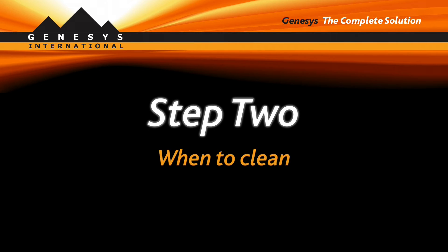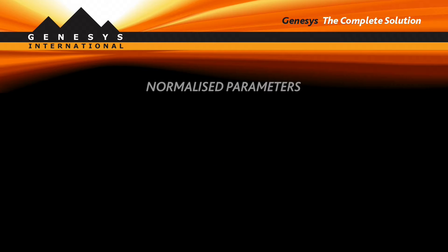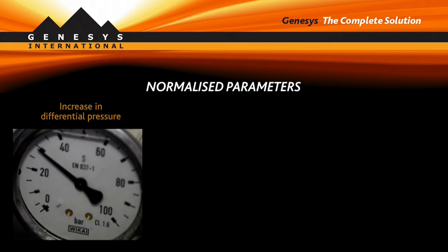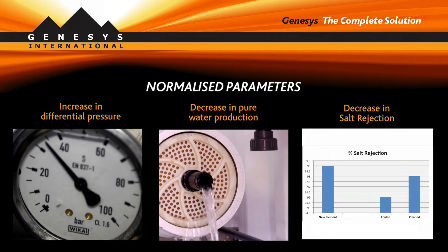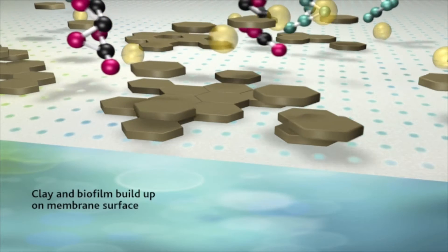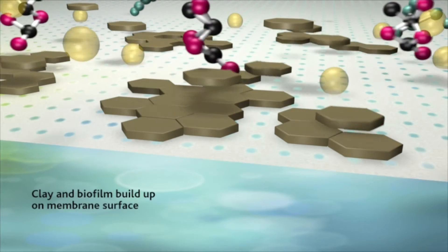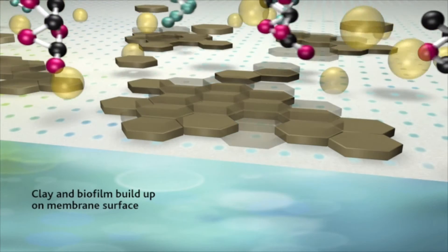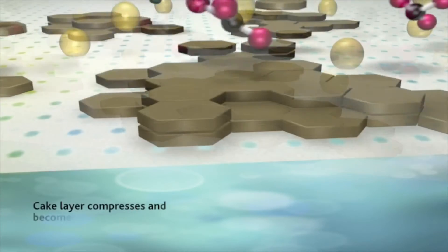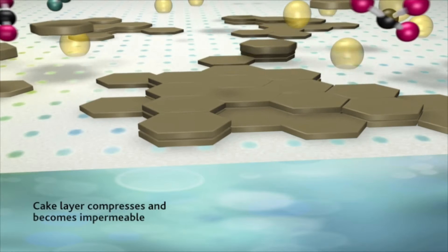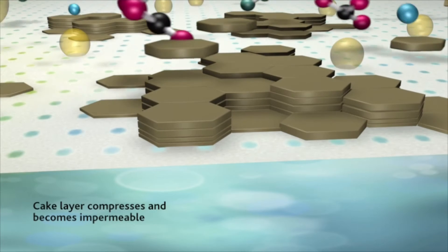Step 2: When to clean. Membrane manufacturers recommend cleaning when normalized parameters change by 10–15%. Delaying cleaning causes foulant compression into the membrane, making removal more difficult. Extra cleaning cycles require more time and chemicals.